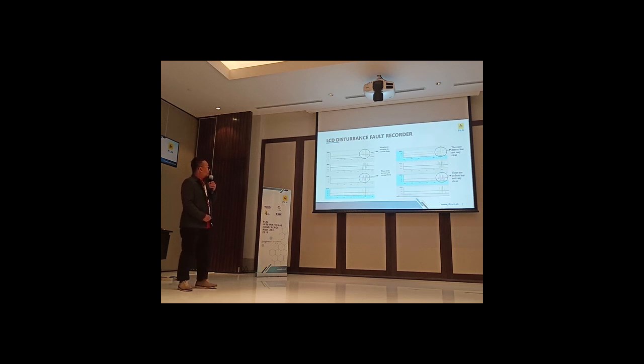Then we zoomed in on the recorder to look at whether something happened on the transmission line or something happened in the relays. But unfortunately, we could not find any footprints. We know that in the recorder we have a footprint for the fault. So we must look for another opinion.